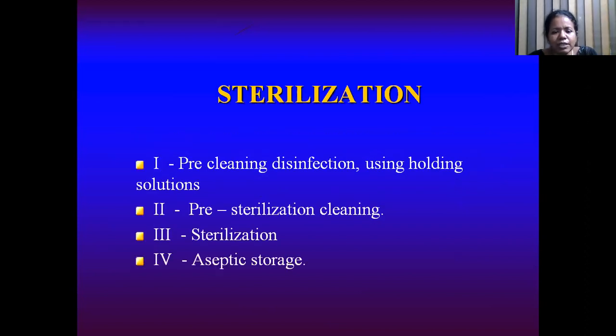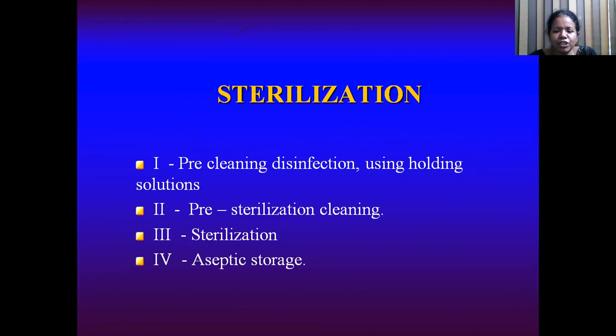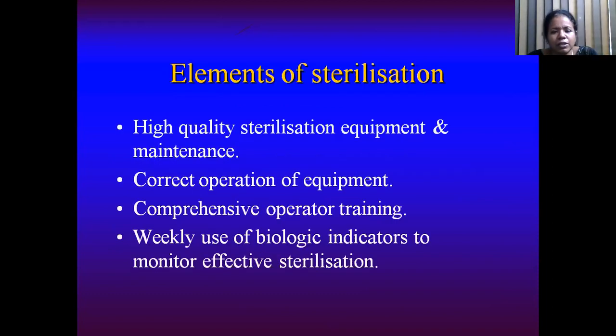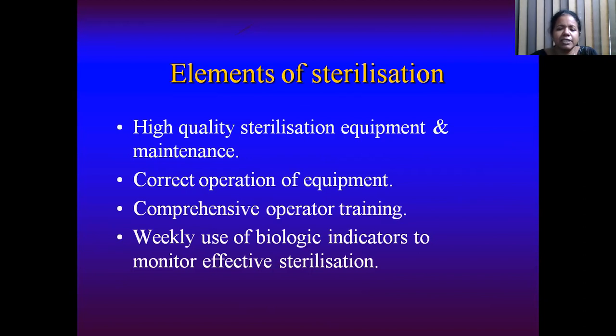Next comes sterilization, which is done in four steps. The first step is pre-cleaning disinfection using a holding solution: after the instrument or surface has been cleaned of residue, a holding solution is used for pre-cleaning disinfection. Then comes pre-sterilization cleaning where the holding solution is removed completely before the instrument is subjected to the sterilization procedure, and finally it is stored aseptically. For sterilization you need high-quality sterilization equipment and maintenance, correct operation of equipment, comprehensive operator training, and weekly use of biologic indicators to monitor effective sterilization. If any one of these is not working, the entire procedure will not be effective.